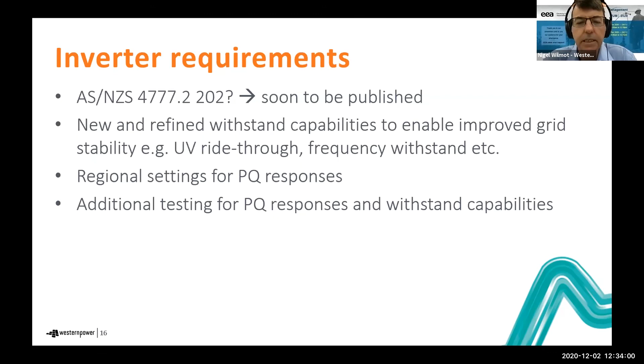In that standard, there have been some improvements, including new and refined withstand capabilities to enable improved grid stability. So undervoltage ride-through and frequency withstand are some of the key areas that have been added. And we've also developed regional settings for PQ responses. So not one size fits all. Different issues are experienced across Australia, and New Zealand has a different voltage range, so again a separate set of settings for New Zealand. And to make sure that these settings work, there's been a lot more detail on how the PQ responses and the withstand capabilities are tested when you certify an inverter.